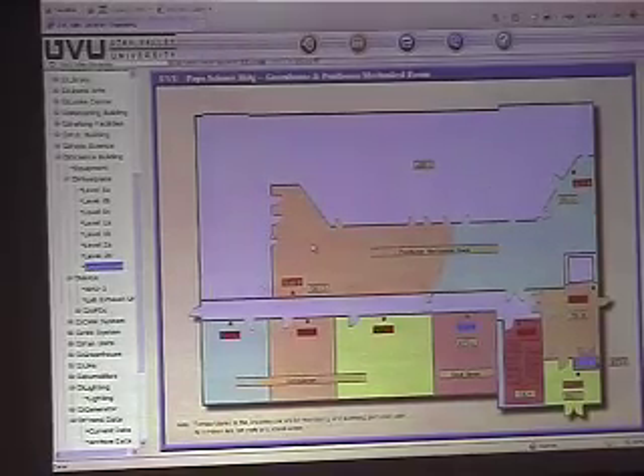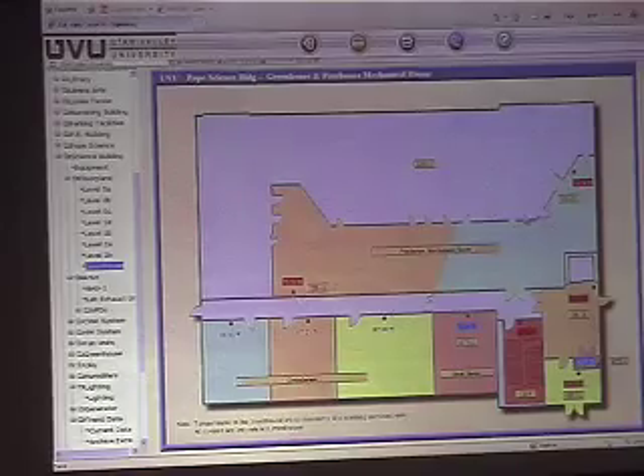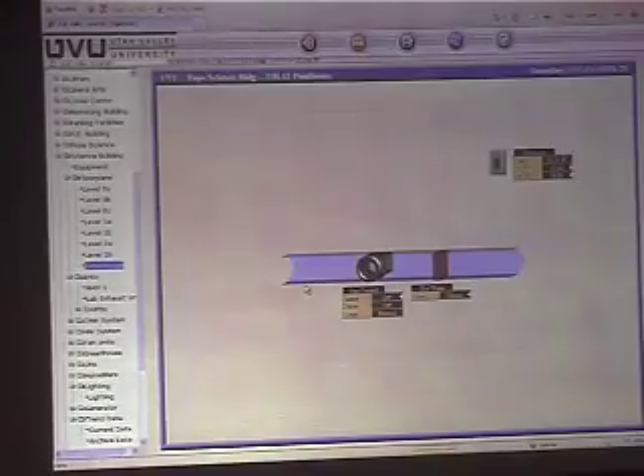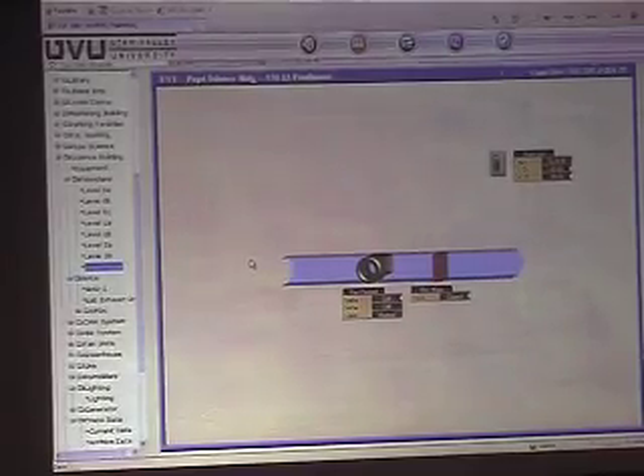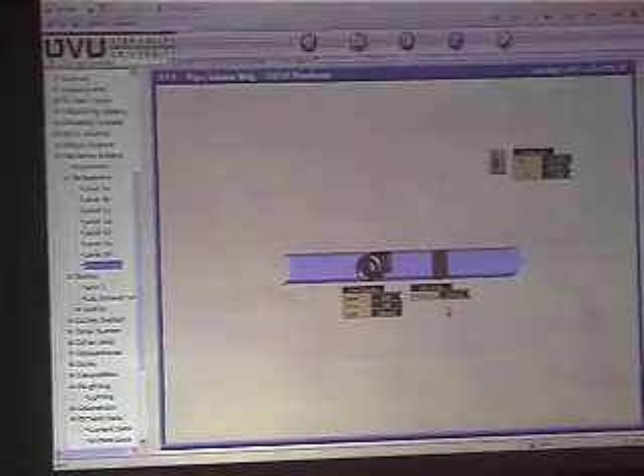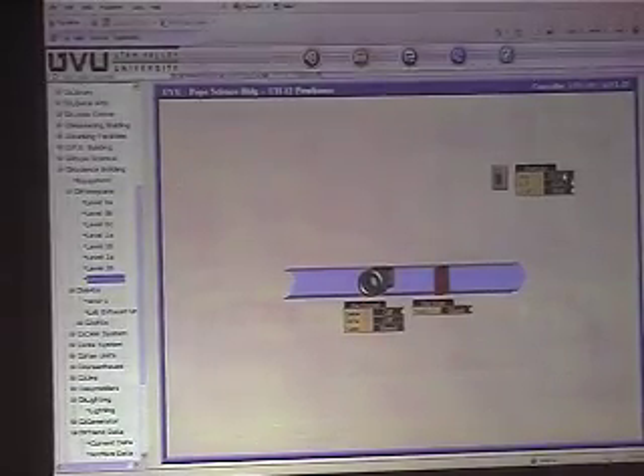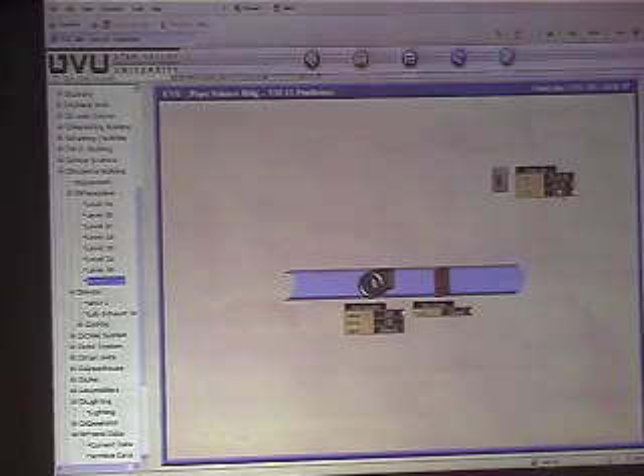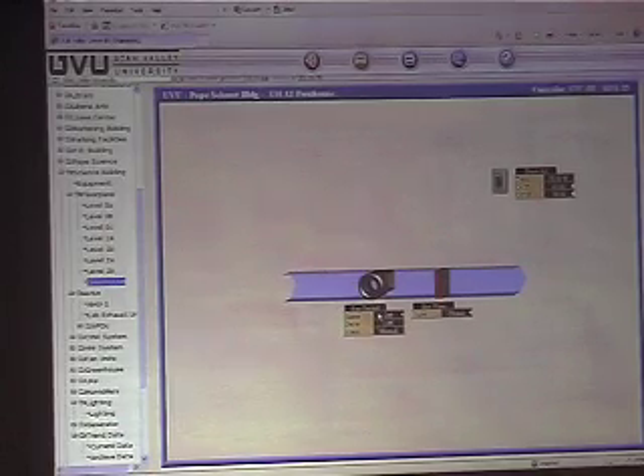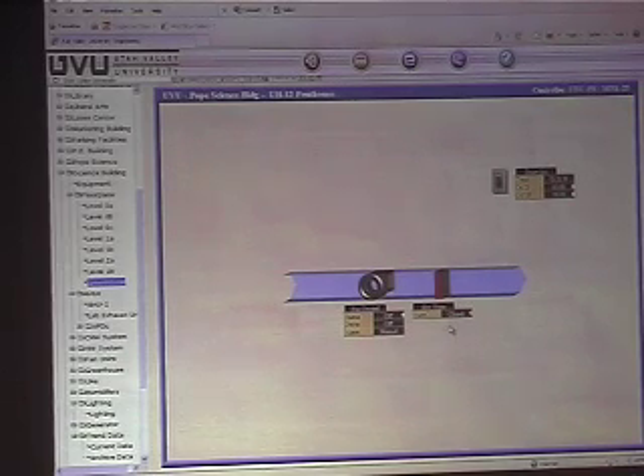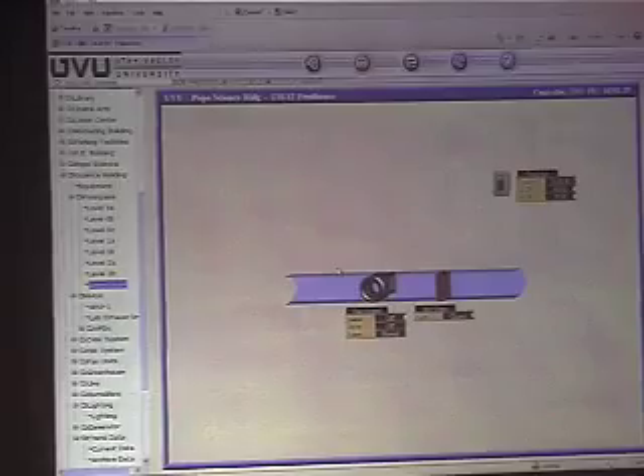And the greenhouse level also incorporates your penthouse. So you've got your unit heaters up here. Click on one of those and you can see, this is typical, there are 13 unit heaters located throughout the building. They're on the DDC system. Space temp, your on set point and your off set point are shown here, as well as your enable, your status and your alarm condition. And then there's a hot water valve on there as well, which we drive open and closed when the fan comes on. So the temperatures for the unit heaters are shown there.